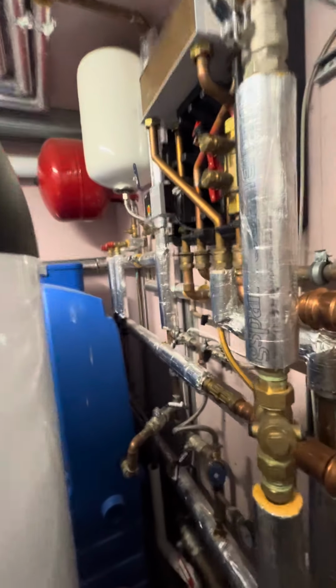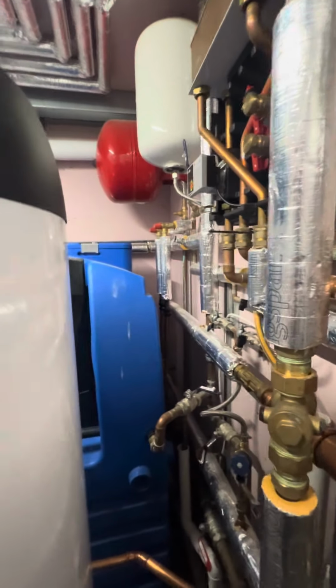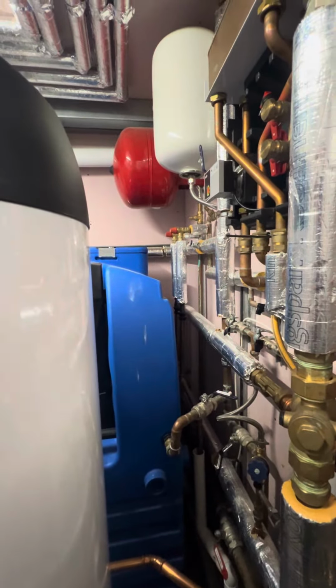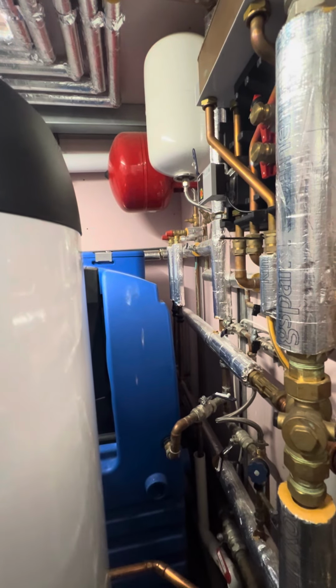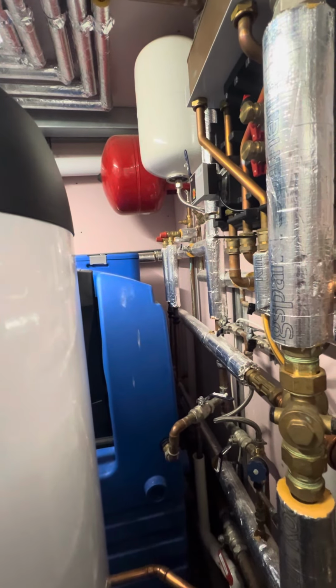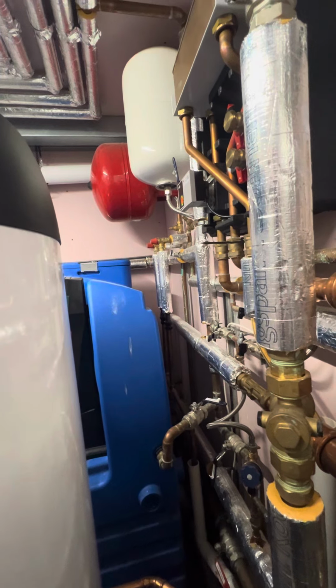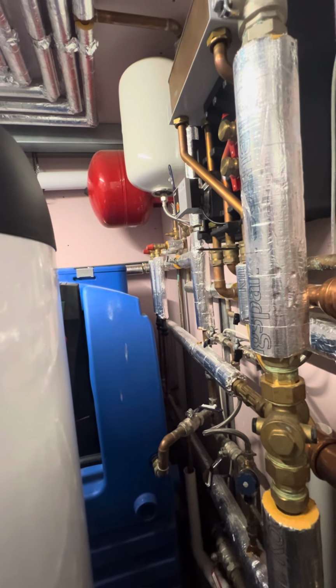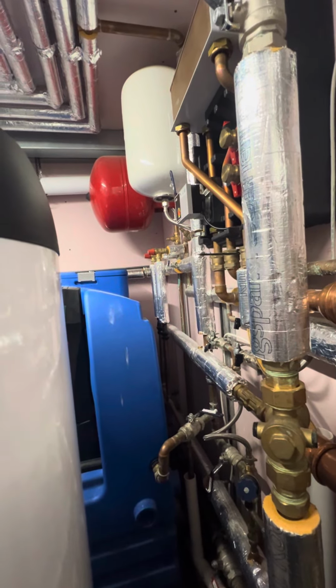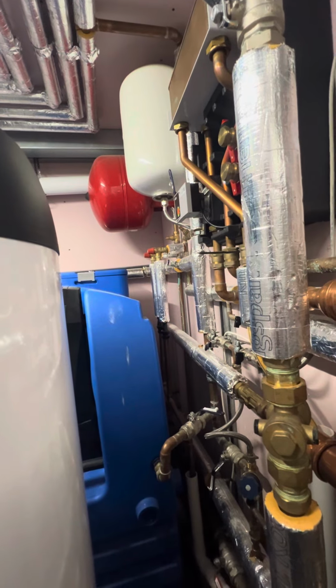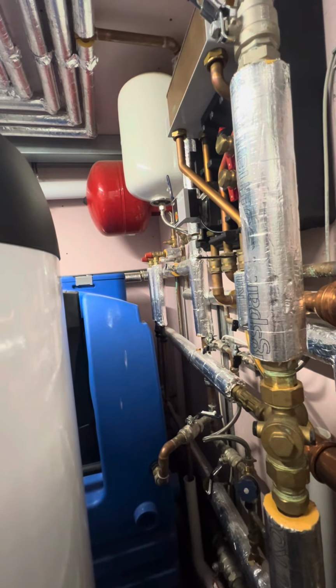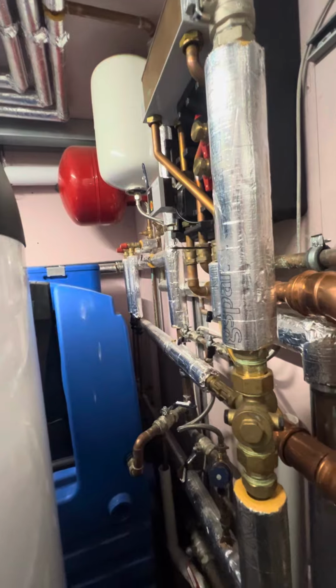But I've done a heat loss calculation on this property. The result was approximately 12 kilowatt. So the second heat pump shouldn't be ever required to come in to boost the central heating, but on the system it can. I would say it's been oversized. However, the Vaillant controls are intelligent enough to hold off that second heat pump from coming on to boost the heating if only 1 heat pump is required and the flow temperature is reaching its target set point in a reasonable time.